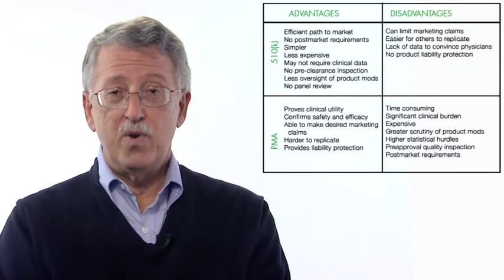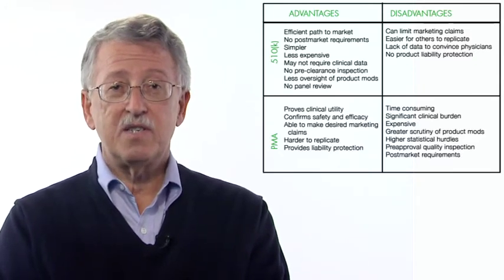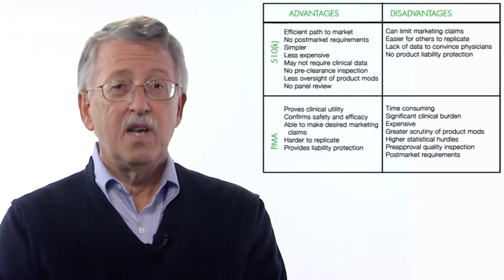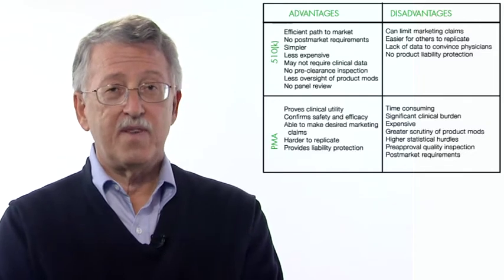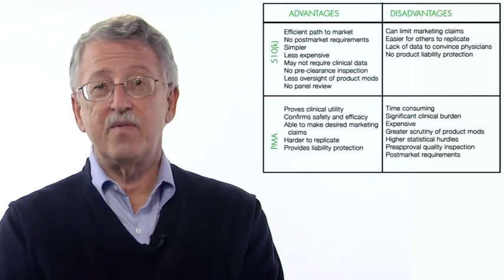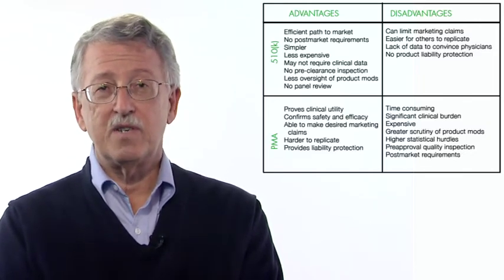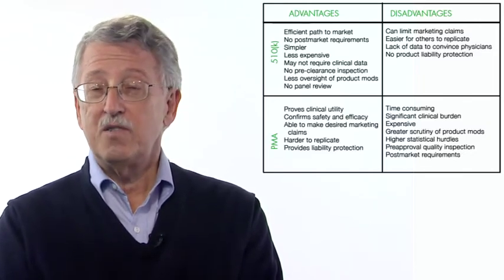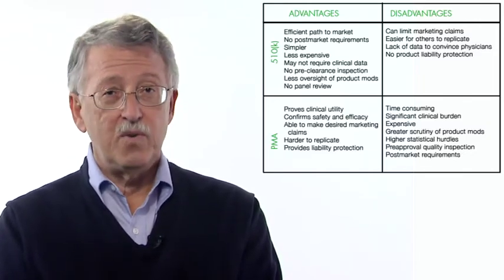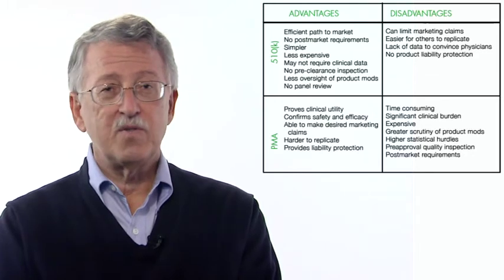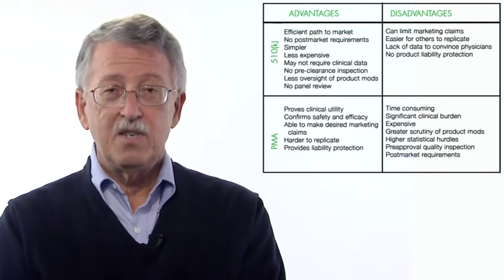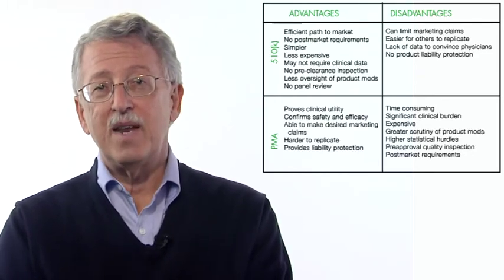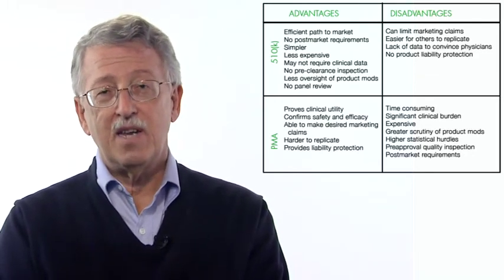There's no pre-clearance inspection. There's less oversight for modifications, which can be a very important consideration. There's no panel review for virtually all 510Ks. So all of those things are benefits to the 510K system.